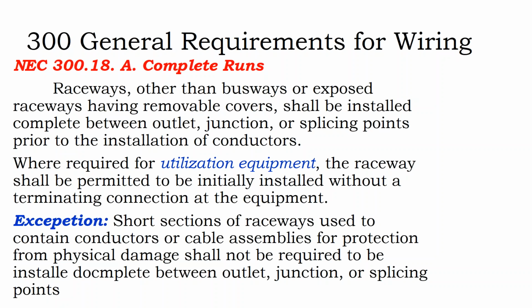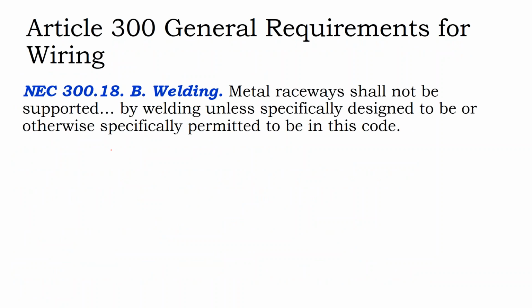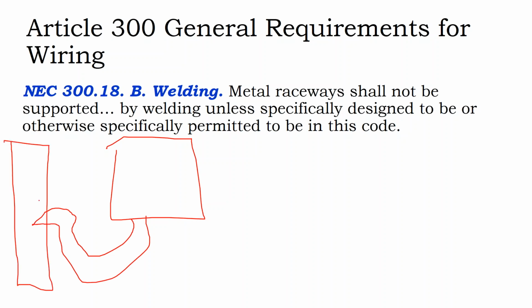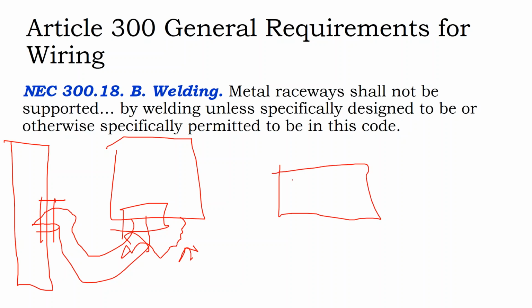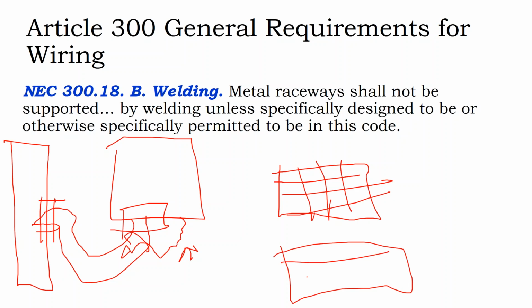So what does all this mean? Well, there's a couple of ways you can use conductors on a site. I'm just going to advance to the next slide to have some space to draw. Basically what it's saying is if you have your junction box and you have a conductor run from your junction box to your inverter, that needs to be a well made up, fitted, continuous run, where you don't have just the junction box and then exposed cables going into the conductor. That part needs to be well made up and fitted. But there may be also cases where, let's say this is your solar array, and then this is a commercial array on a flat roof, so you have another section of your solar array, and you need conductors to go from point A to point B.